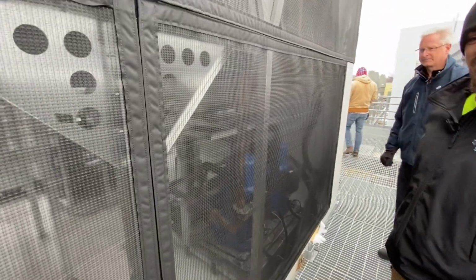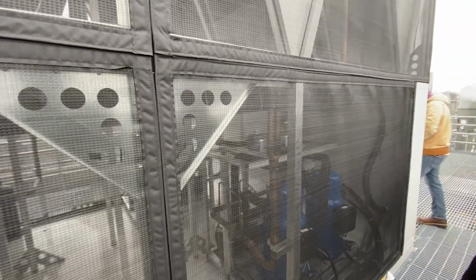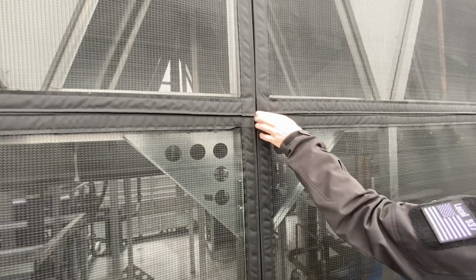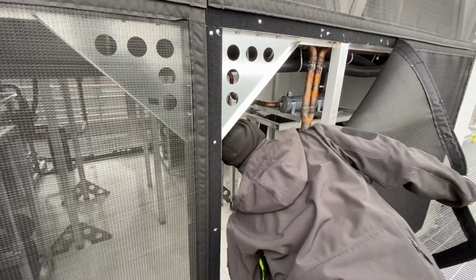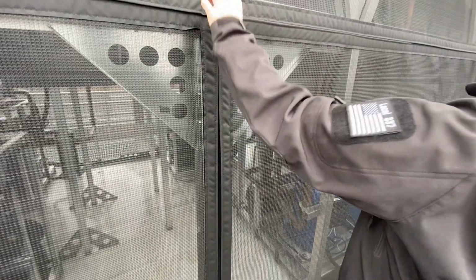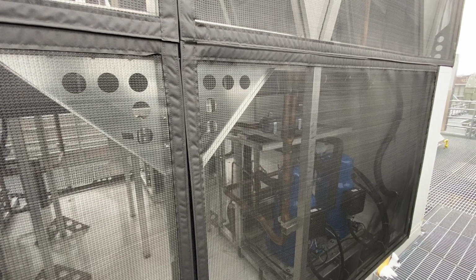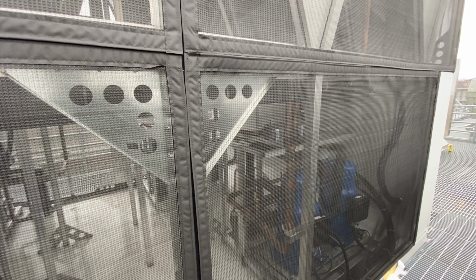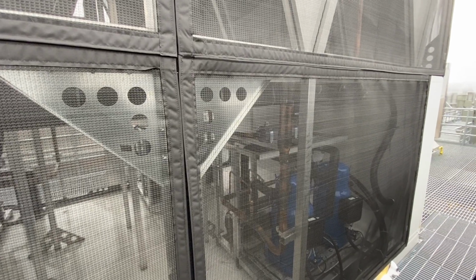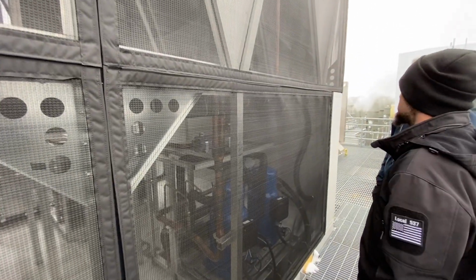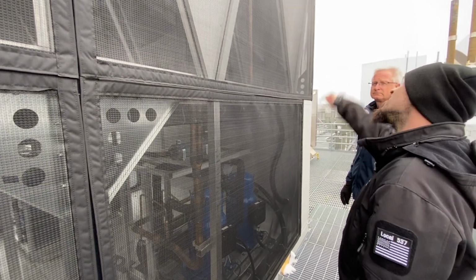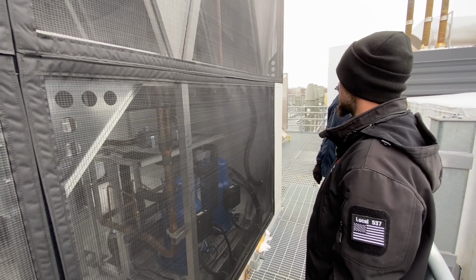Yep. You have 4 circuits of cooling. VFD compressors or modulating compressors, 2 stages each. Pretty straightforward. Condensers that I believe are microchannel. Yep, microchannel condenser coils. So cleaning the coils, pretty much just hose them down. No need for any chemical or product or anything like that. They tend to deteriorate the aluminum. Okay. So just good pressure water, push all the stuff out, and then also down through the top.